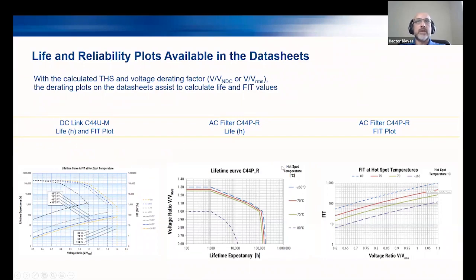In the case of the C44PR, which is our AC filtering capacitor, we split the plot: we have the life calculation and the FIT plot. Keep in mind that there is another factor here: you see the voltage ratio. It's the VDC voltage applied to the capacitor divided by the rated voltage of the capacitor. So you can see that derating is very important, not only in temperature but also in voltage. The closer you approach a better derating factor, the higher the possibility that you can reach levels of 100,000 hours. So it's very important to keep in mind that not only heat but also voltage derating is important for extending the life of the capacitor.